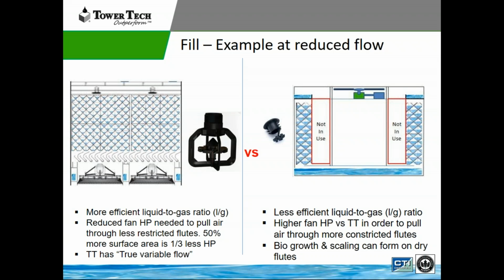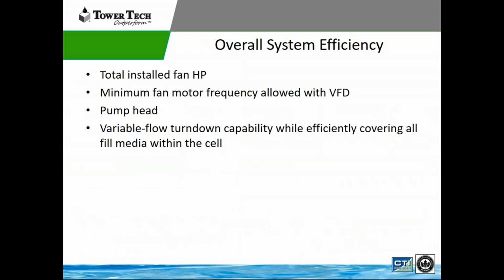The conventional system on the right, what's happening is on the weir system, when that gets to 50% flow, we're no longer using that side of the fill. So at that point, it's basically the same liquid to gas ratio. So they're not gaining much efficiency at part load when they run reduced flow through their system. So we're going to look at the overall system efficiency. So the total installed horsepower, the minimum fan motor frequency allowed by VFD, the pump head, we're going to analyze that, and a variable flow turn down capability while efficiently covering all the fill media within the cell.